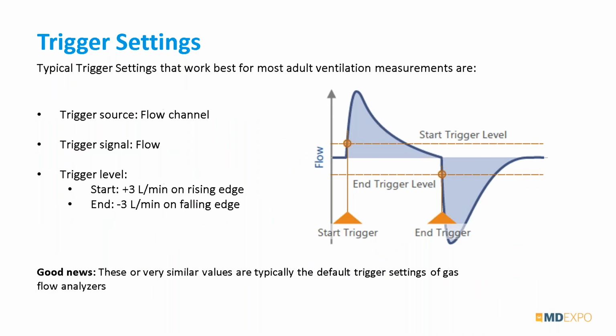That's why, if you go into the trigger settings of your gas flow analyzer, you will see that by default the trigger settings are on the flow curve, with trigger levels around 3 to 5 liters per minute as a start trigger and a stop trigger. And these triggers work well in, I would say, 95% of your applications. So that's probably why you guys never had to touch them. Okay, so this is really important to know. In many cases, you don't have to touch them.